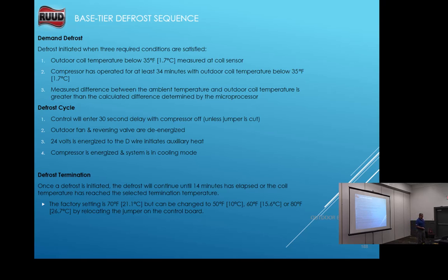In our defrost cycle, the control will enter a 30-second off delay for the compressor. The outdoor fan and reversing valve are de-energized, and 24 volts is energized to the D wire. So we bring on some auxiliary heat for Granny so she doesn't get cold air blown on her when we go into cooling mode outside, right? It's pretty much the same defrost cycle for our base tier, mid tier, and high tier.